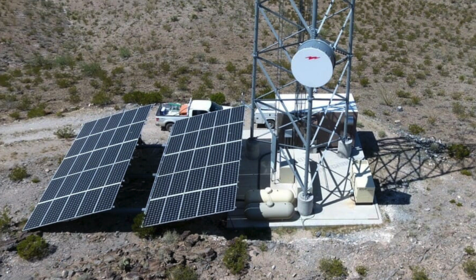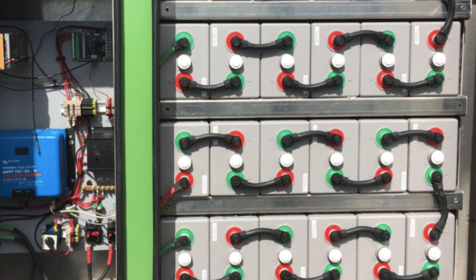This watchdog system can reset or restart equipment such as a generator or even a communications backhaul. For instance, backhaul reset via SCADA can be done manually, albeit remotely from your headquarters. Or, as most of our customers prefer, one can program the FlexSCADA to automatically reset the backhaul when there is a power failure or the equipment itself trips out for any number of reasons.